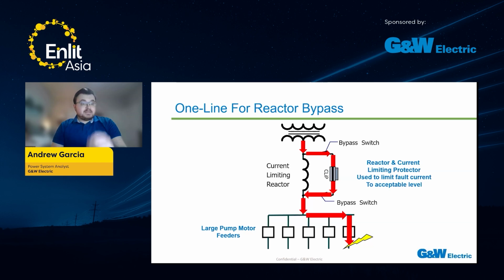So how would that reactor bypass look? You can see an example in the one line below where the current limiting reactor is in parallel with the CLIP. The reason why this works is because the CLIP is a low impedance device by its nature under normal operation, meaning that all of the current and fault current will initially just go through the CLIP. And once the CLIP triggers and this becomes open, all that fault current will then just get limited by the current limiting reactor, and you would maintain system uptime as a result.